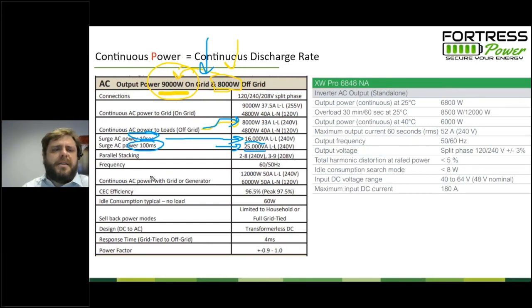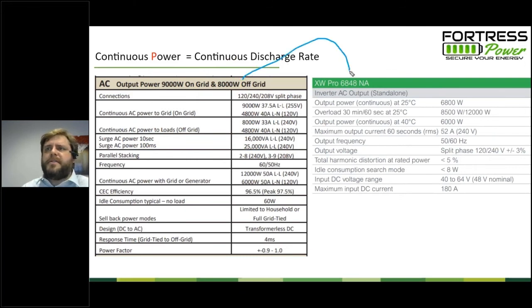There's a little bit more going on behind the scenes with these surge mode or burst mode settings that is worth being aware of. We're going to get into that in a minute, but just for comparison's sake, here's a different battery inverter, and this is a 6,800 watt inverter. They don't necessarily have exactly the same thing like a 10-second or 100 millisecond rating, but they do have a 30-minute and a 60-second rating. So for 30 minutes, this 6.8 kilowatt inverter can deliver 8.5 kilowatts of power, and for 60 seconds, it can deliver 12 kilowatts of power.